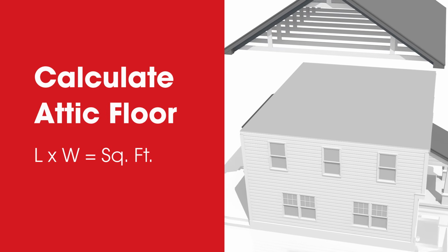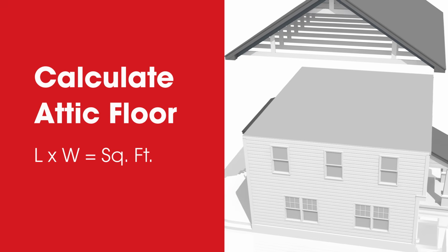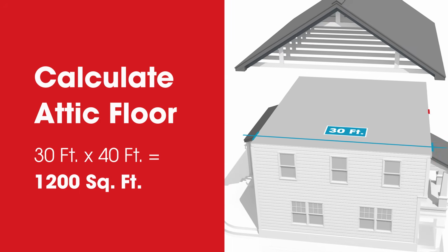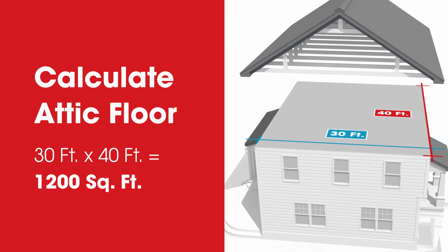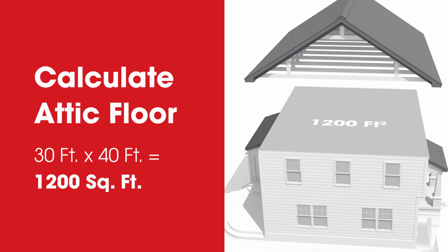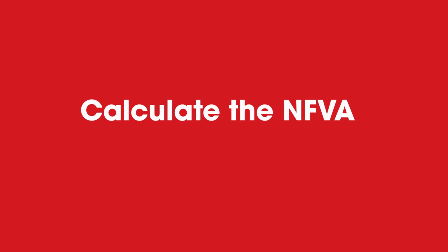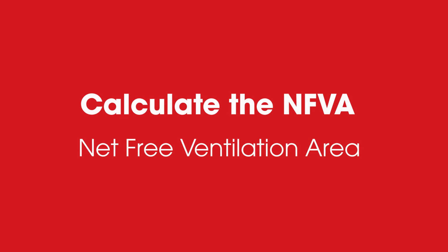First, calculate the square footage of the attic floor space. For example, the attic in this illustration is 30 feet wide and 40 feet long, which totals 1,200 square feet. Next, calculate the NFVA. NFVA stands for Net Free Ventilation Area.